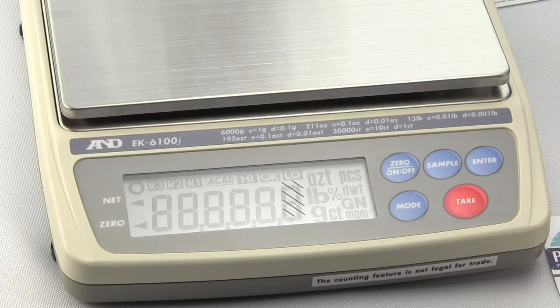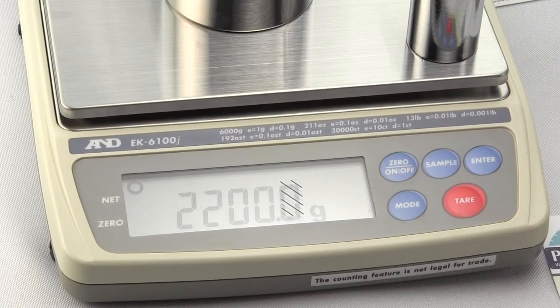Scale returns back to the weight mode. And we put our 2,000 gram weight. And you can see with the 2,000 gram weight it does very well also. So it is user selectable. And you can see when I put this weight in all the quadrants, it's very repeatable.